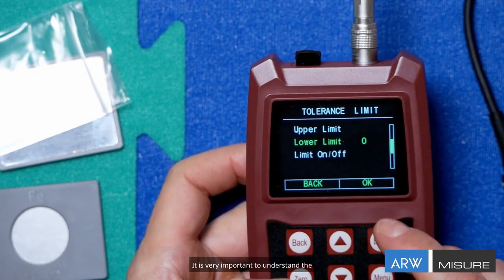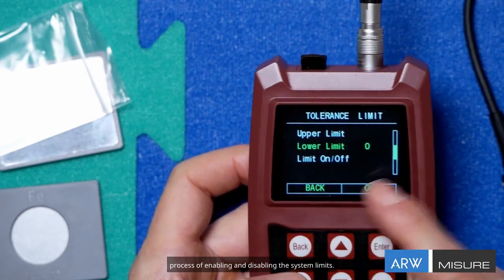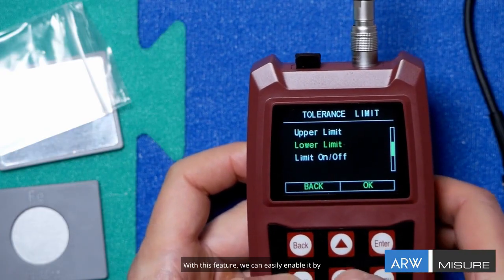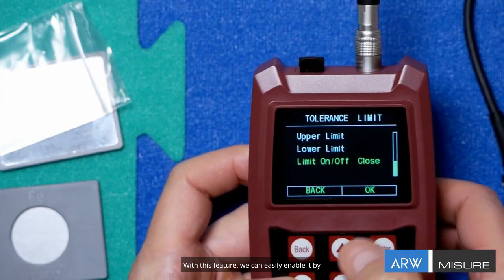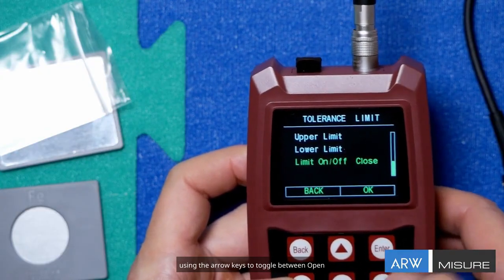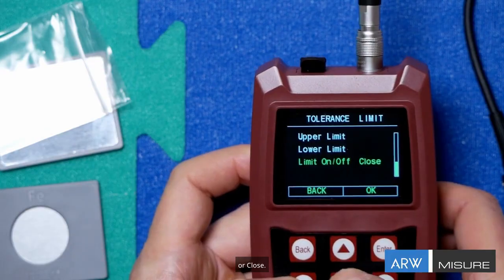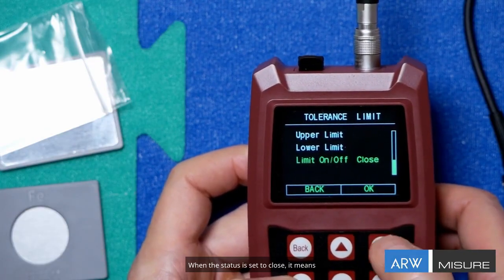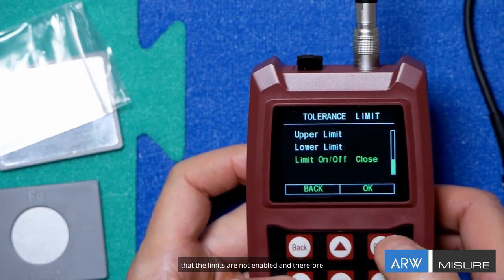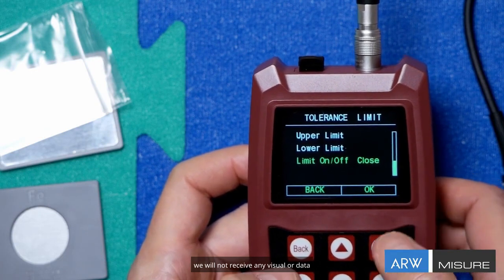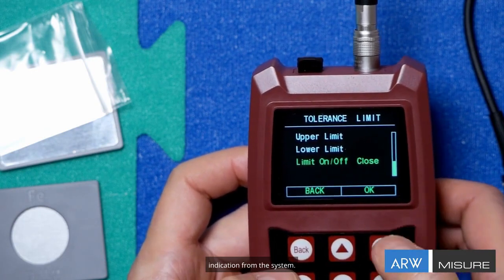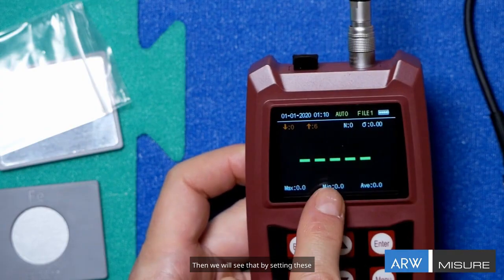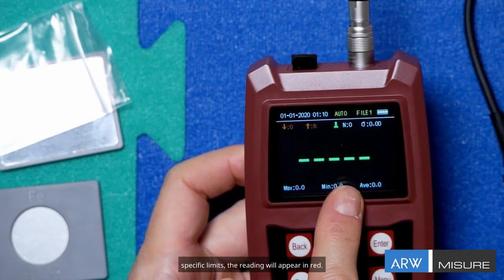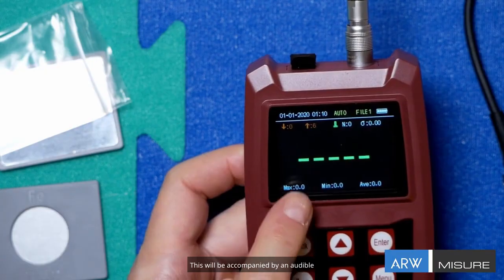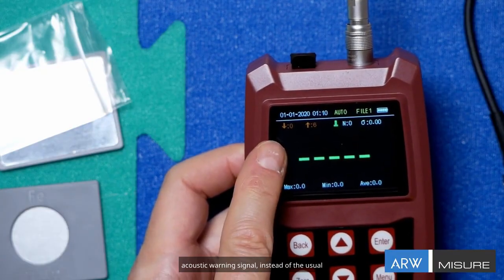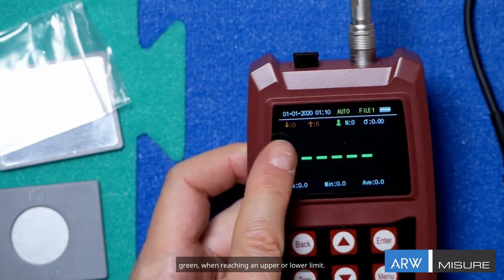It is very important to understand the process of enabling and disabling the system limits. With this feature, we can easily enable it by using the arrow keys to toggle between open or close. When the status is set to close, it means that the limits are not enabled and therefore we will not receive any visual or data indication from the system. Then we will see that by setting these specific limits, the reading will appear in red. This will be accompanied by an audible acoustic warning signal instead of the usual green when reaching an upper or lower limit.